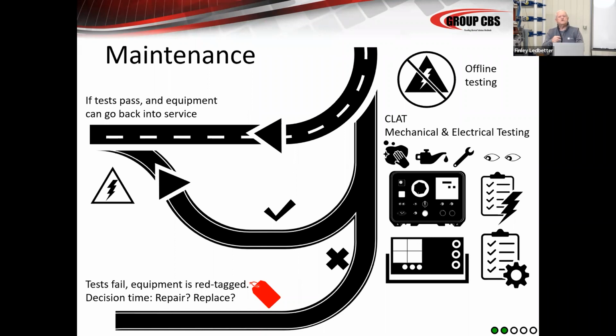And you continue to do this 5, 10, 15, 20. At this point, this equipment could be up to 25 years old. And it's going right back onto course every 5 years. You had very few problems. When you've had a problem, we call it red tag. Some people actually use a red tag. And that's a situation to where the breaker needs to go out to a repair shop, or you need to have someone come in and look at it, whether it's the original manufacturer or qualified repair service. That's your choice. Depends upon what's available to you, what relationships you have, and did you come out of this feeling good about the original manufacturer's service team.